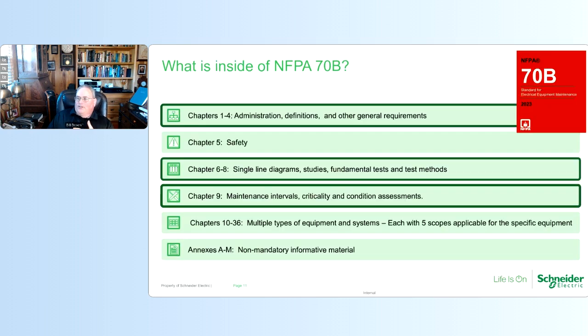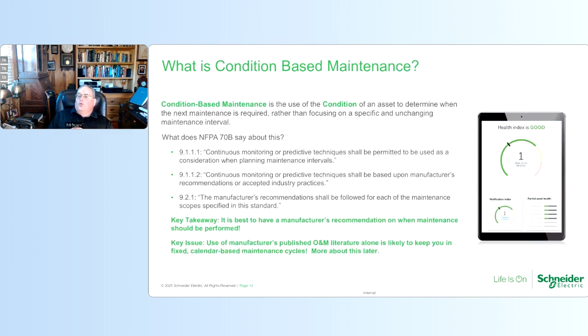So when we talk about condition-based maintenance from an NFPA 70B perspective, we're really talking mainly about NFPA 70B Chapter 9, which covers maintenance intervals, criticality, and condition assessments. So, what is condition-based maintenance? Simply put, this is the use of the condition of an asset to determine when the next maintenance is required, rather than solely focusing on a specific and unchanging maintenance interval.